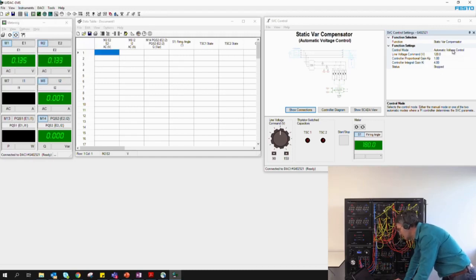This gives us access to the automatic voltage control function shown here. When in this mode, we have to set the line voltage command, at what voltage we want the SVC to keep the receiving end, and the proportional and integral parameters to control how the controller responds to changes. These default values are good, but you can play with them to see how they impact controller behavior.